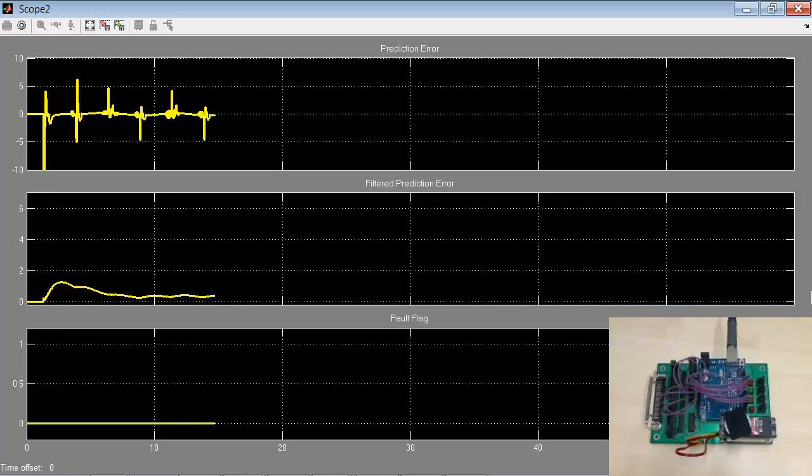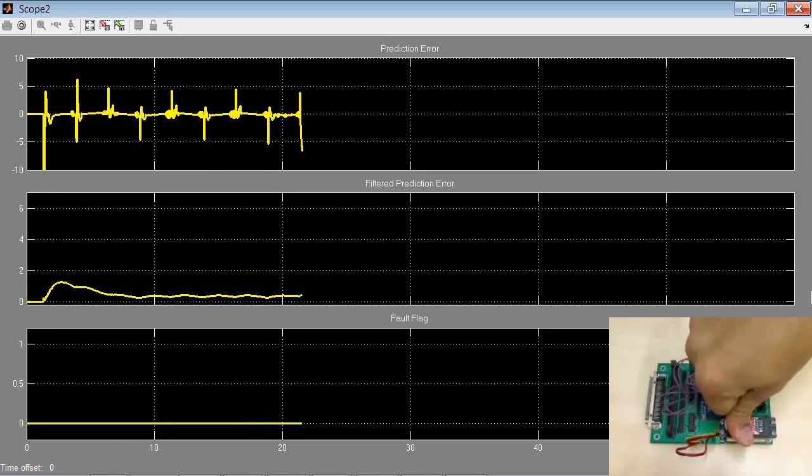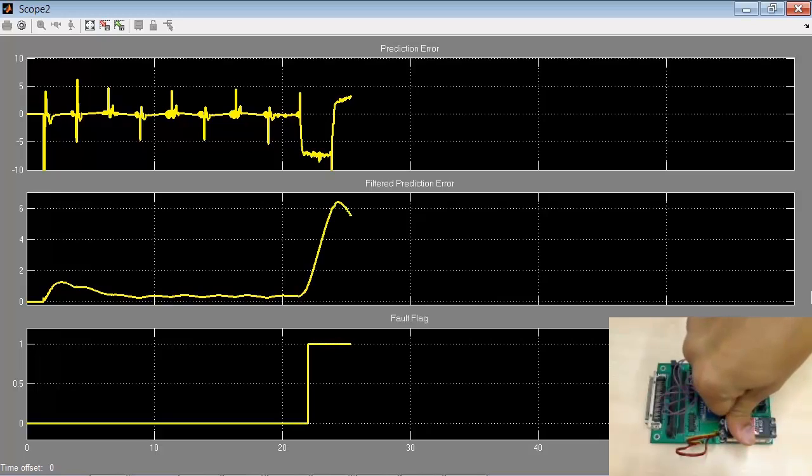By the time we disable adaptation at 10 seconds, the parameter estimation converges and the prediction error is close to 0. When we apply a load, the prediction error shoots up and the fault flag gets set.